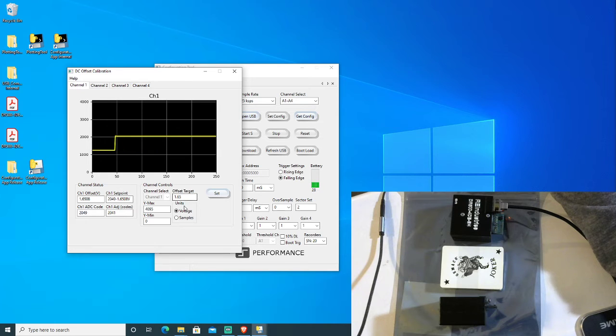So you have an option to do voltage configuration. It auto-tunes itself. The time does increase as gain increases. The gain does add complexity to the offset tuning under the hood, but most of the time sample settings are more than enough, and these are direct sets, so they're very simple.